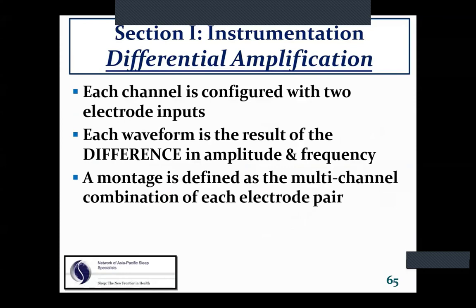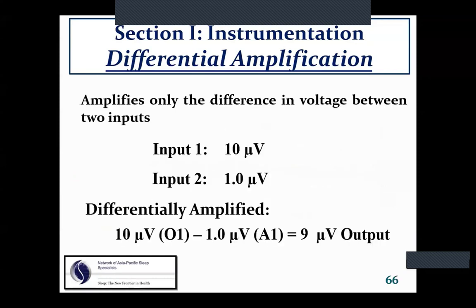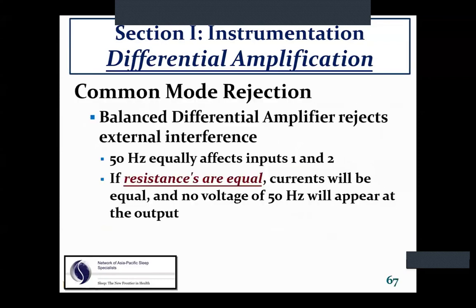Each channel is configured with two electrode inputs. Each waveform is the result of the difference in amplitude and frequency. And then a montage, as you know, is defined as a multi-channel combination of each electrode pair. So differential amplification applies input 1 minus input 2, so you'll get that output voltage from the difference of those two electrodes.